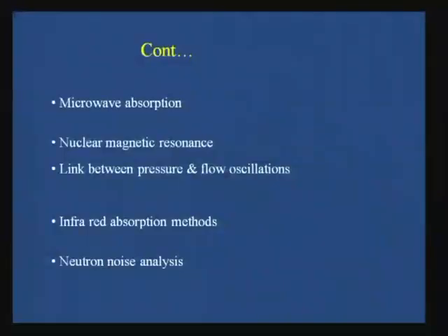Electrical impedance again works for low quality flows. The beauty of infrared absorption is that it works for high quality flows. So, if we have to go for high quality flows, it is very good for air-water, steam-water and such flows. This is one.